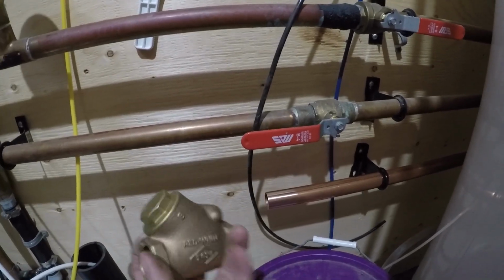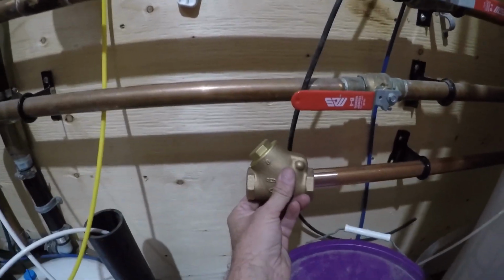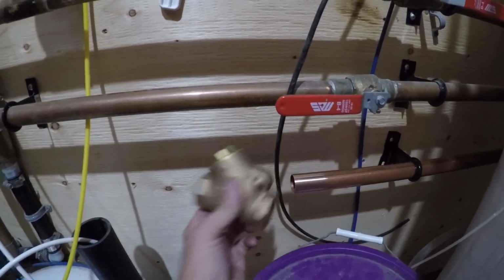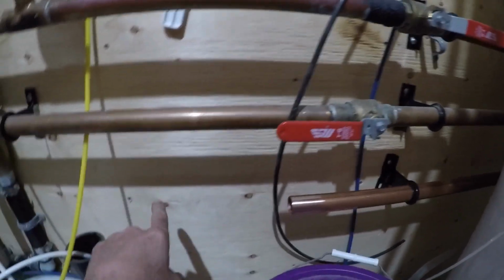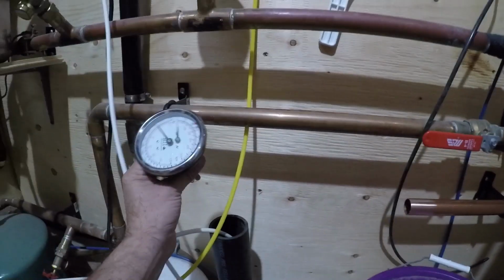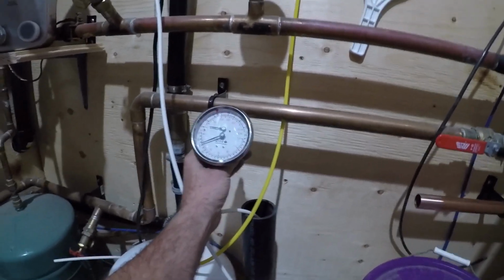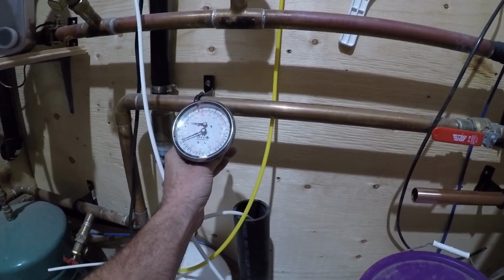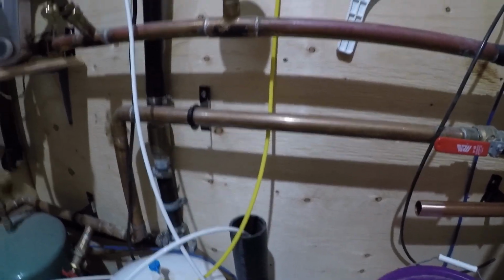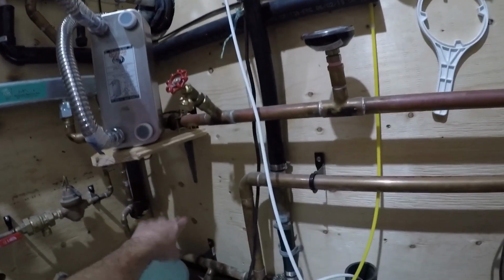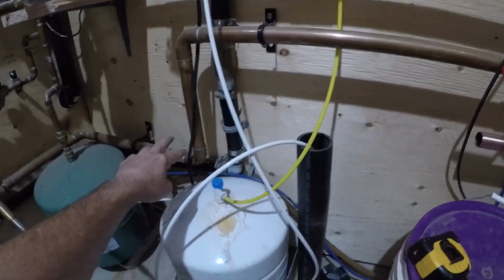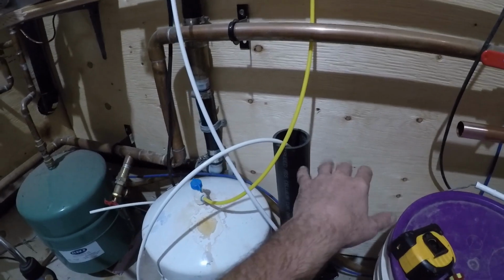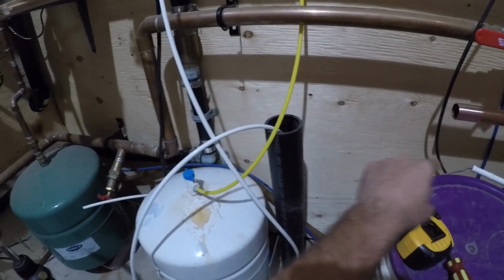Basically now at this point I need to put in - how does this go? - a one-way valve or check valve here, and then we're going to add a shut-off valve, and then a spout for a temperature and pressure gauge. At that point, when we move this down, it'll connect into there, and then we have to do the whole return side. So again, coming off of that, we need isolation valves for the circulation pump, and then wrap around and connect into that lower side there still.